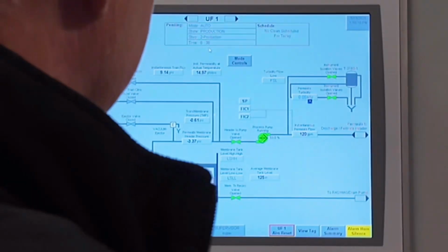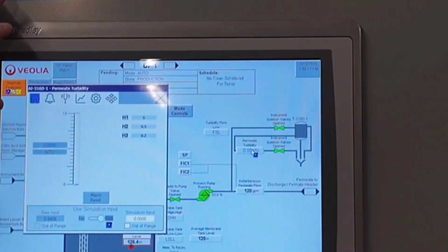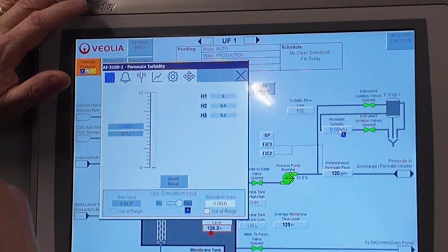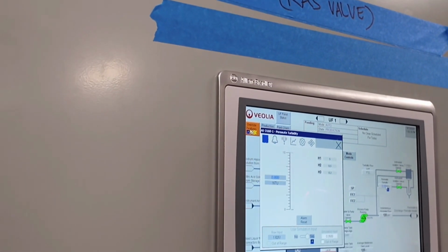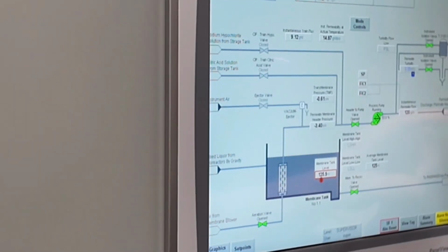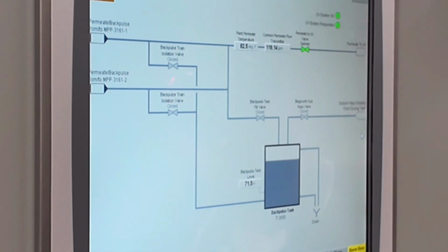Now the water should be flowing to the turbidity meter. Let's have a look what's going on here. So we put a preset in there. Remember, yeah, the simulator. So I'm just going to see what it shows you, the raw value, because it's been sitting around a while. If it goes above 0.5 you get an alarm and all that. So I'm just going to wait till it stabilizes. So it's still high. So now it's going out. It gives you a common thing. So that's going out to UV.